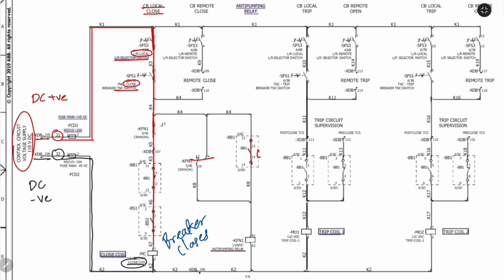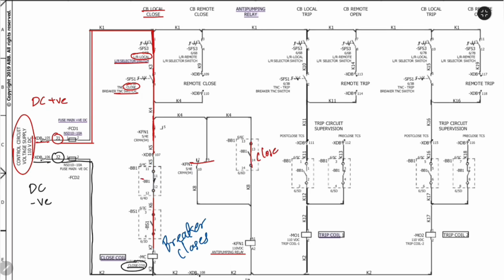Immediately after closing, the breaker auxiliary contacts change state. The normally closed contacts open, removing power from the closing coil. This prevents the coil from remaining energized, even if the operator accidentally holds the TNC switch in the closed position.